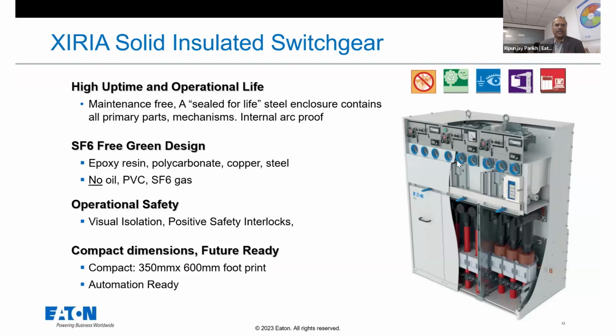Eaton is a pioneer in SF6-free switchgear. We have a facility and system that is entirely solid insulated, meaning all the current-carrying paths and live equipment are completely enclosed in a solid insulated encapsulation and then covered in a steel tank. The advantage is there's no SF6 gas, and no leakage on account of SF6, so you're not damaging the atmosphere. It gives the same compact footprint as a normal ring main unit.